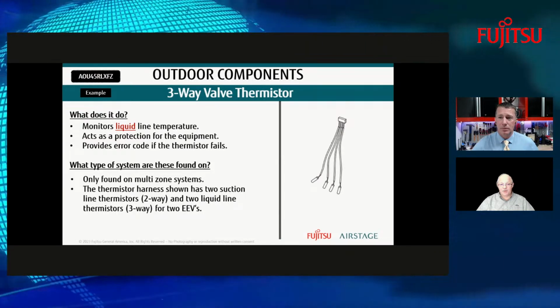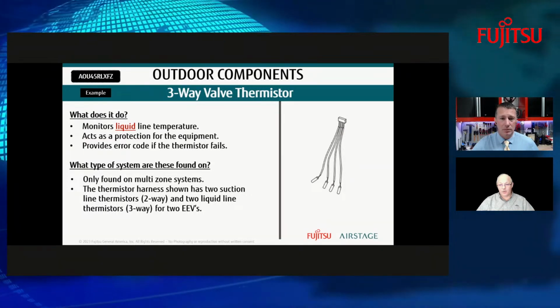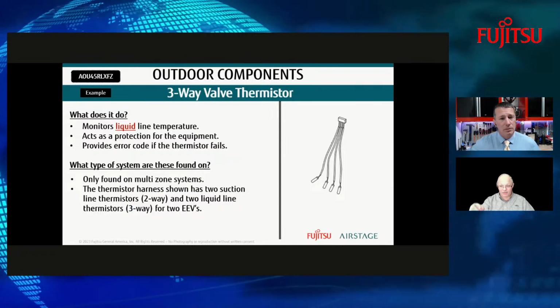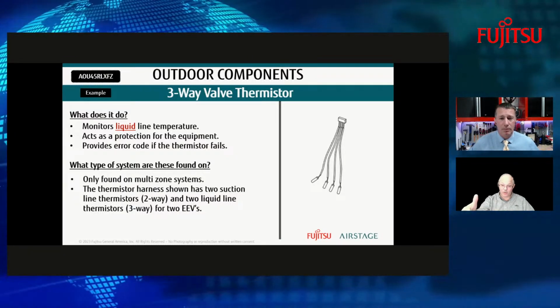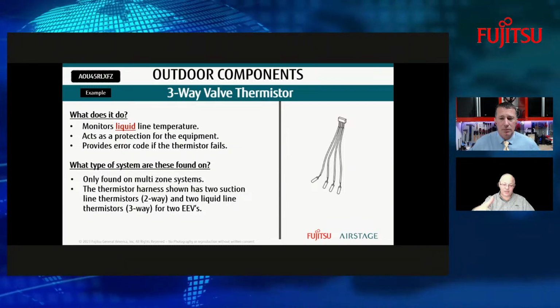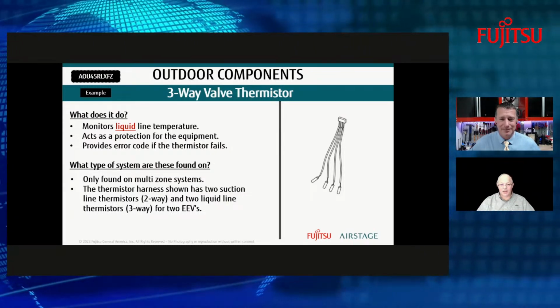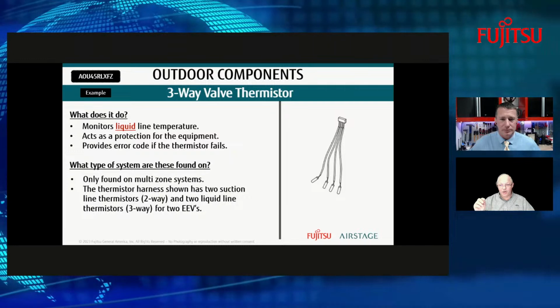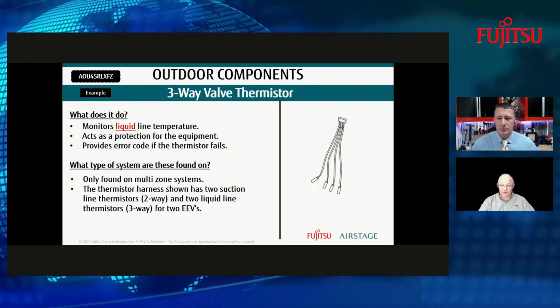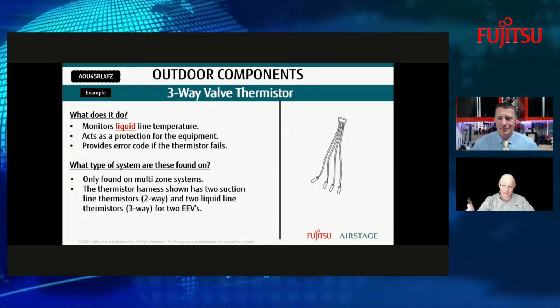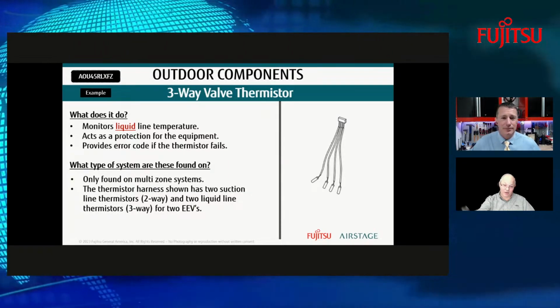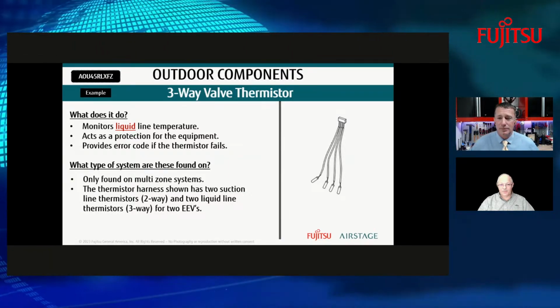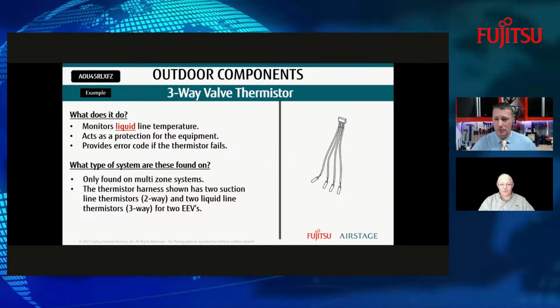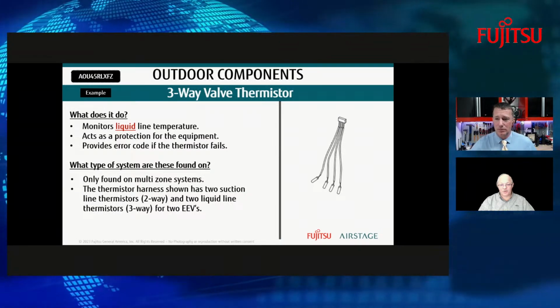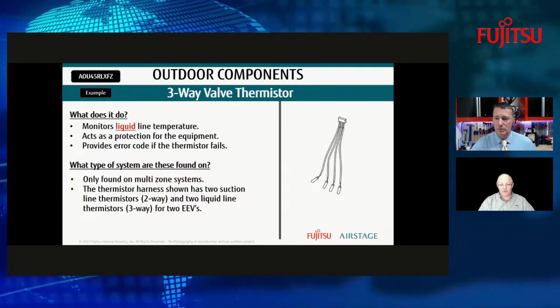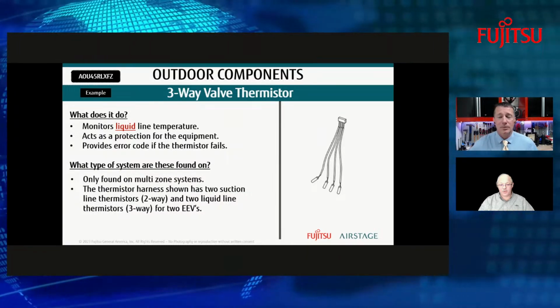All right. So we got a 3-way thermistor. This one is monitoring the liquid line. So again, when you're looking at these, it's like, well, which one's which? Well, you could trace these out to see which one's going to which line. Again, if you were to have just one of these go bad, you get the whole harness. Yeah, makes sense. You're looking at 4 of them here. So that's what the 3-way valve would look like on the thermistors. So you have 2 suction line thermistors and you have 2 liquids.